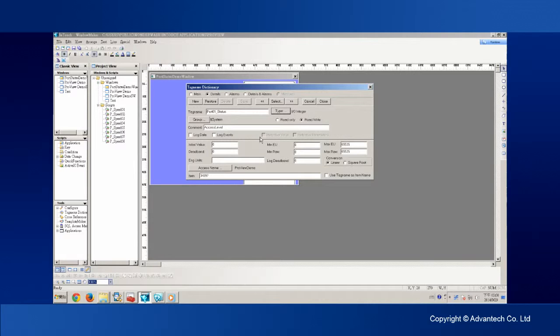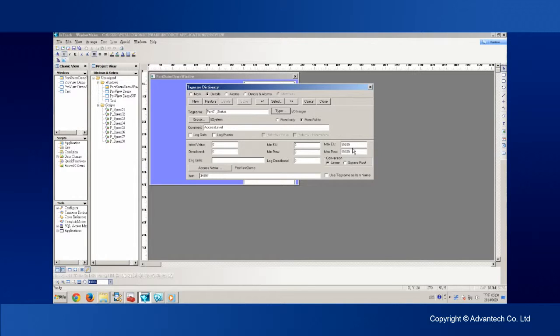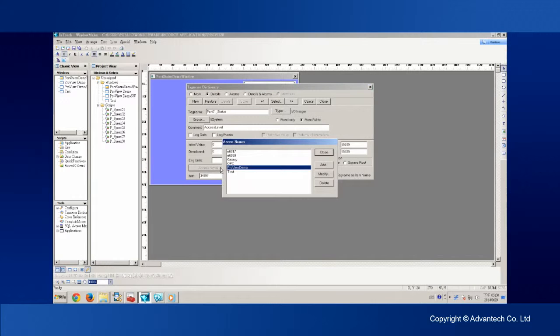From the user menu, we found out that the data type and length for the port 1 status is represented by 4 hex characters. So we set the maxEU to be 65535. Then we select the pre-configured access name, ProViewDemo.